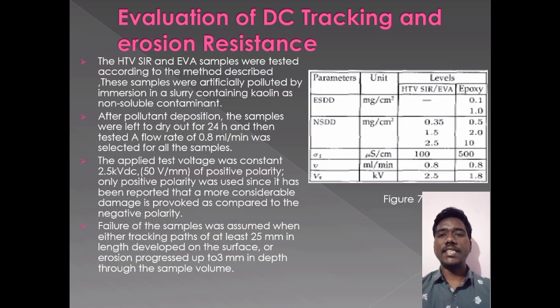Tracking and erosion DC evaluation. Two different test methods were employed during DC evaluation. In the first method, the samples were artificially polluted by immersion in a slurry containing kaolin as a non-soluble contaminant. After pollutant deposition, the samples were left to dry out for 24 hours, then tested. Several non-soluble deposit density levels were adopted, ranging from 0.35 to 10 mg per square centimeter, which is consistent with those previously predefined during AC evaluation.